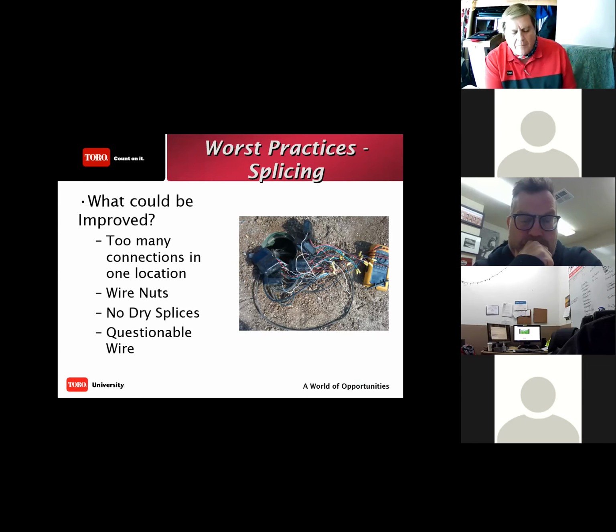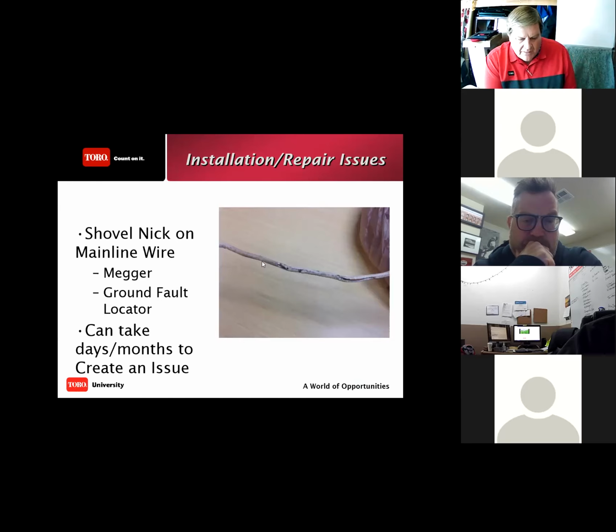That's a total mess. This one here, the copper wire got compromised. The corrosion occurred so badly that the copper wire inside that wire is missing. This took me, I'm going to say, close to a week to find. A nick in the wire will ruin the wire. So the wire conductor is so important. The condition of it must be clean.